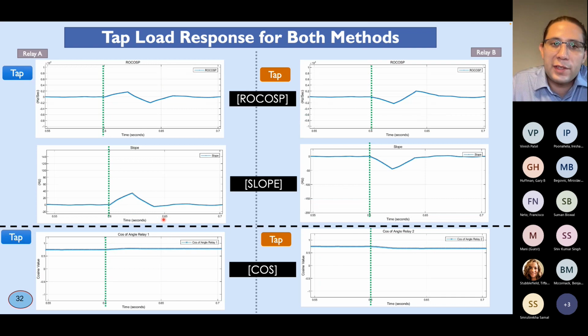Now a critical test is the tap load. Tap loads are in between a distribution line, so they might go undetected, and that's the big question. By implementing the 2 methods we tested, starting with the bottom one, we can see that when we have a fault, there is a discrepancy in both ends of the line, but it is not big enough to cross the zero boundary and be detected.